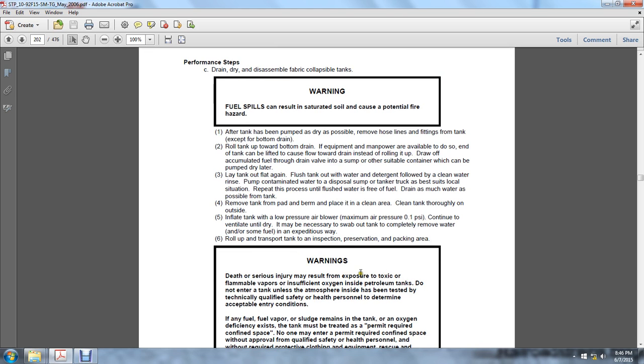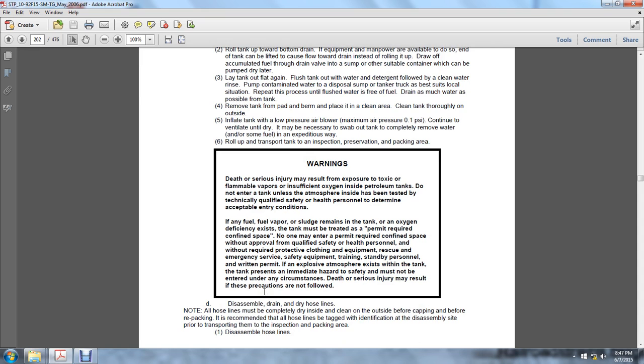Warning: death or serious injury can result from exposure to toxic, flammable vapors or insufficient oxygen inside petroleum tanks. Do not enter the tank unless the atmosphere has been tested by technically qualified safety and health personnel to determine acceptable entry conditions. If any fuel vapor or sludge remains in the tank, or an oxygen deficiency exists, the tank must be treated as a permit-required confined space. No one may enter a permit-required confined space without approval from qualified safety and health personnel, and without the required protective clothing and equipment, rescue and emergency service, safety equipment, training, standby personnel, and a written permit. If an explosive atmosphere exists within the tank, it presents an immediate hazard to safety and may not be entered under any circumstances. Death or serious injury may result if these precautions are not followed.